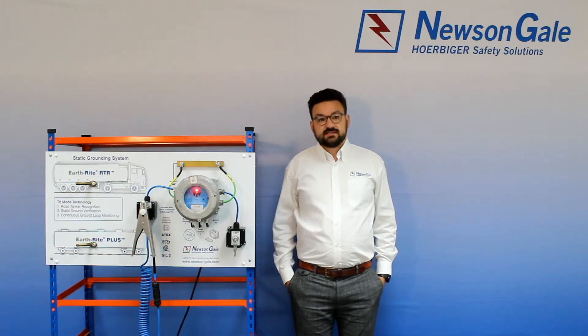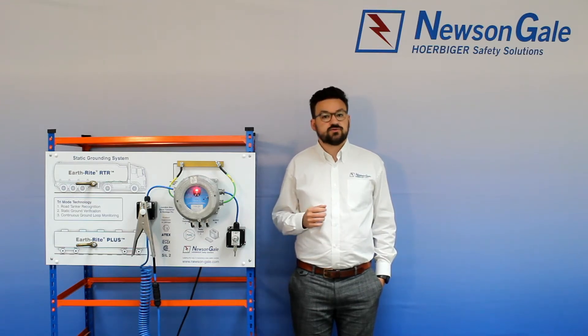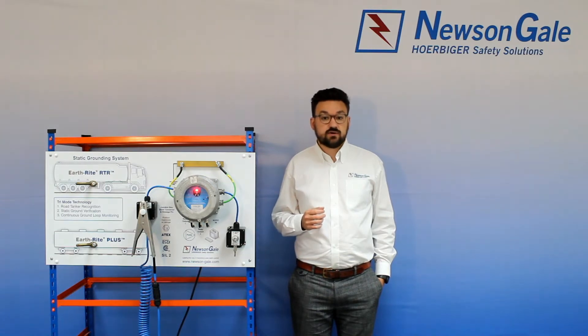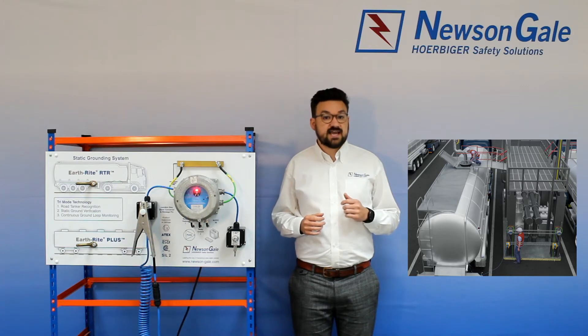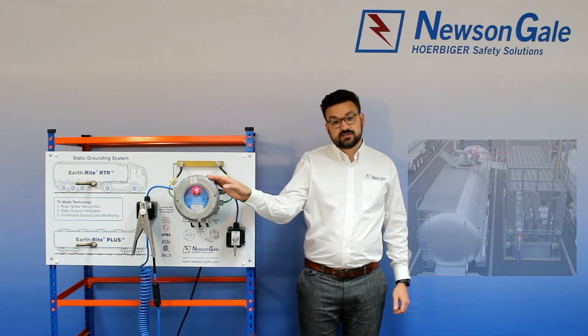The potential risk of static charge accumulation on road tankers and tank trucks can be managed through the correct installation and proper use of the Earth-Rite Road Tanker Recognition System from Newson Gale, ensuring suitable grounding and preventing operation of equipment in unsafe conditions. In this video we are going to explore the principles of operation of the RTR system and, although predominantly the same as Newson Gale's MGV system, the RTR is gantry mounted rather than a vehicle installed system.